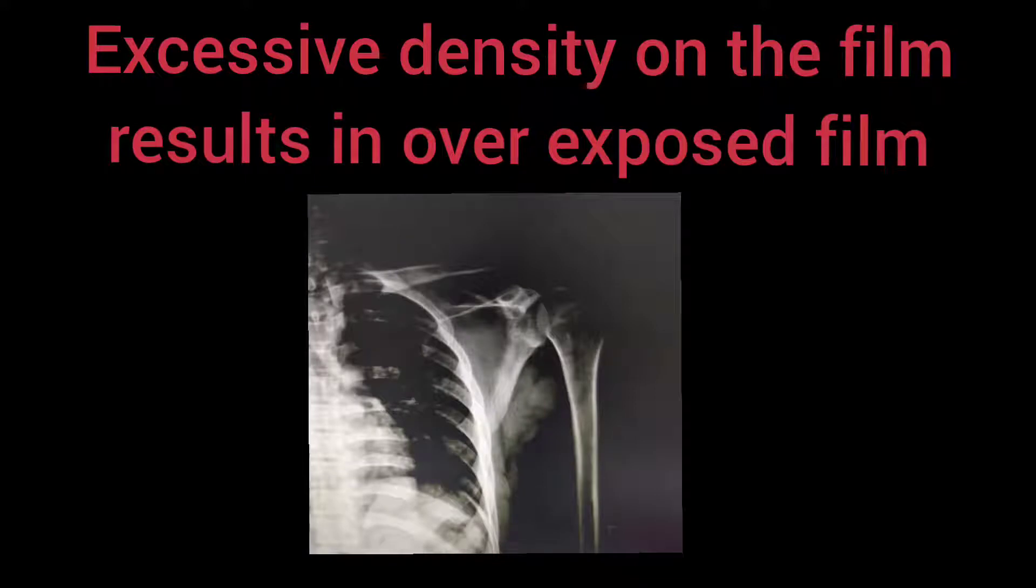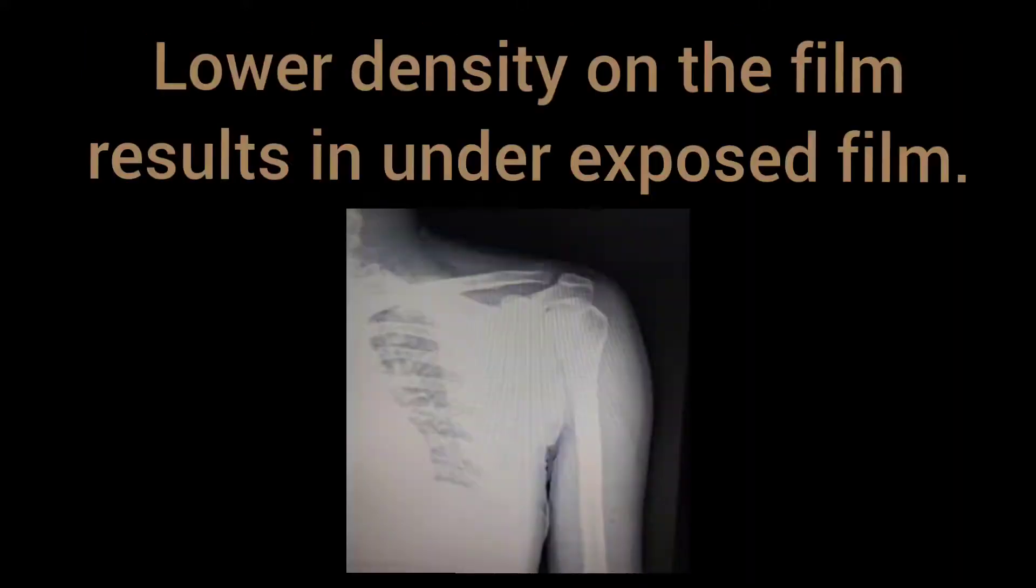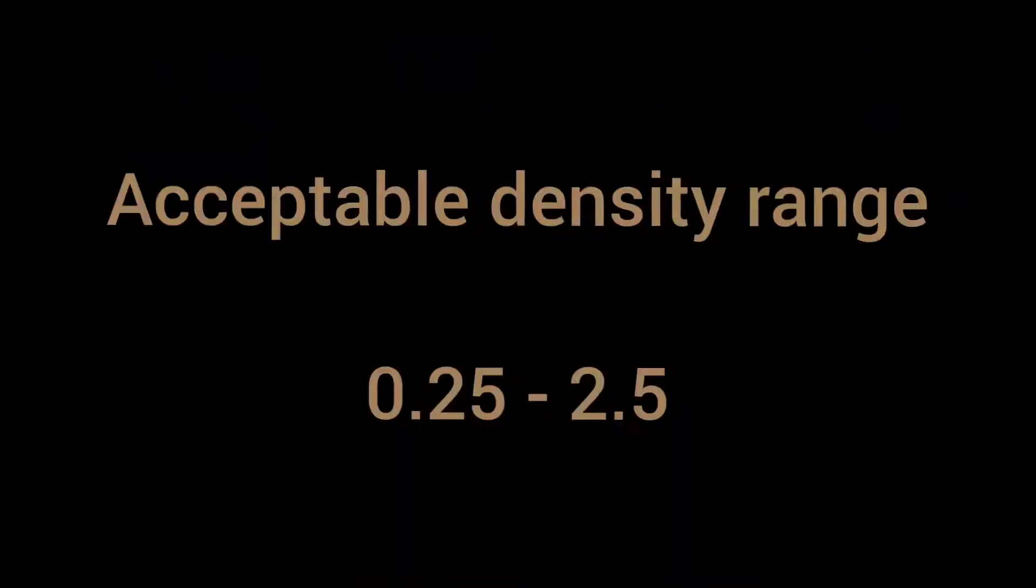Excessive density on the film results in overexposed film and lower density on the film results in underexposed film. The range of acceptable density is between 0.25 to 2.5.